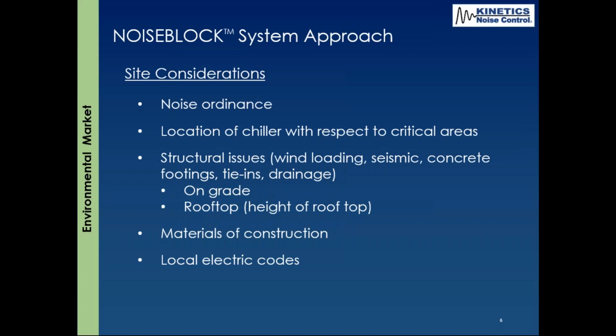So the first thing our Kinetics reps or internal team looks at is whether there's a noise ordinance involved. Was the problem at the property line with neighbors complaining? In this case, it wasn't the property line—it was actually a walkway five feet away from the opening of the equipment yard. So the location of the chiller with respect to critical areas was key: the critical area was that walkway, five feet away.